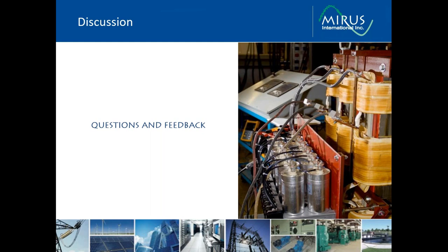A question here about a manufacturing plant with multiple sources of harmonics. What would you recommend to put in place in front of a three-phase UPS to filter harmonic distortion? So it sounds like it wouldn't be for the UPS, but maybe for a load that is supplied from the UPS? Okay, so most UPSs are designed with some form of harmonic mitigation on the input.